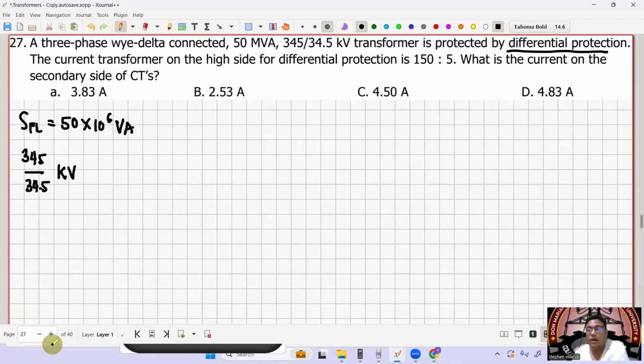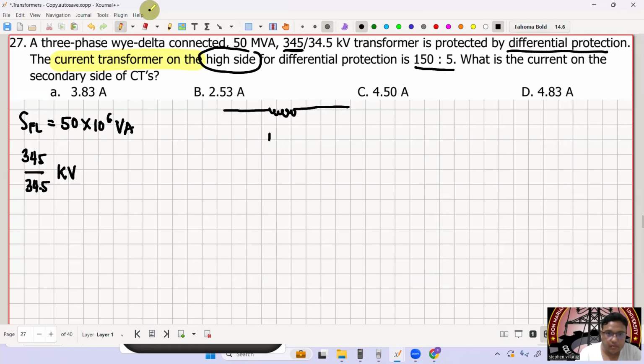A 345 over 34.5 kV transformer is protected by differential protection, meaning it uses current transformers and potential transformers. The current on the high side for differential protection is 150 is to 5. Take note, where is the current transformer connected? It's on the high side, meaning it's connected on the 345 side, on the wye.